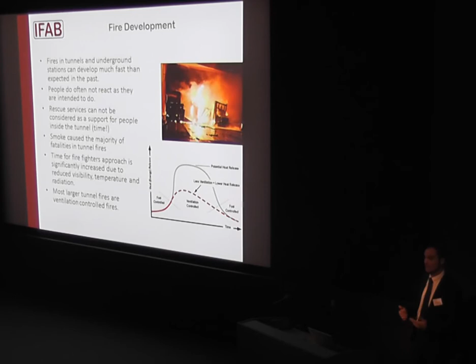We know from many incidents that smoke is the danger - smoke causes the majority of fatalities in tunnel fires. This is also a problem because the time for firefighters to approach the fire is significantly increased due to reduced visibility. If you have no visibility, it's just like driving a car on a highway through fog - there's no way you can drive that fast as with clear visibility. I can tell you from Germany, we have no speed limit on the highways, so it can be much faster.